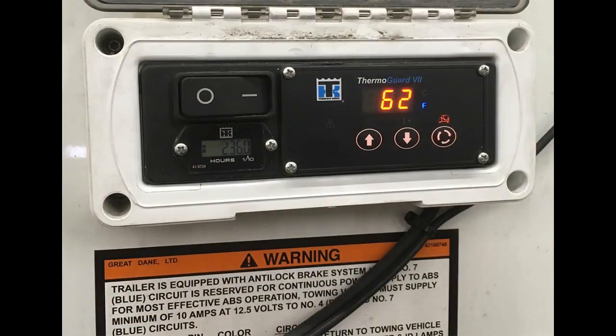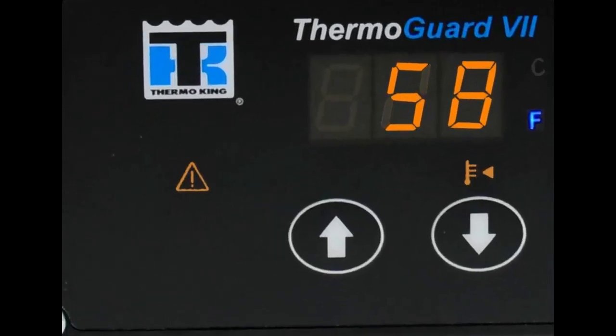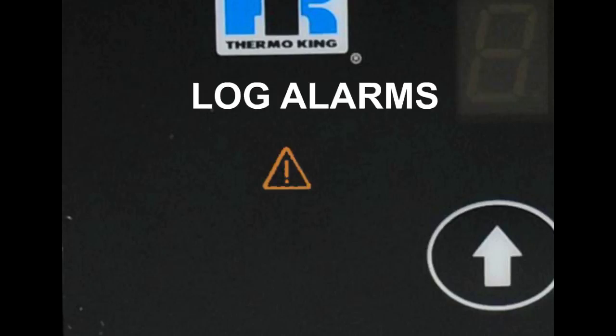Make sure the box is at or near the desired temperature before loading. The Thermo King's controller monitors a number of sensors and variables and under some conditions will produce an alarm. There are three types of alarms: log alarms, check alarms, and shutdown alarms. Log alarms give you notice to take action before a condition impacts unit performance — some maintenance items are log alarms. Any log alarms present will show for 30 seconds each time the unit is turned on, and the alarm icon will light up in yellow for those 30 seconds.